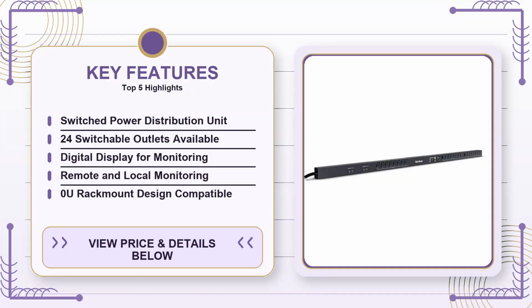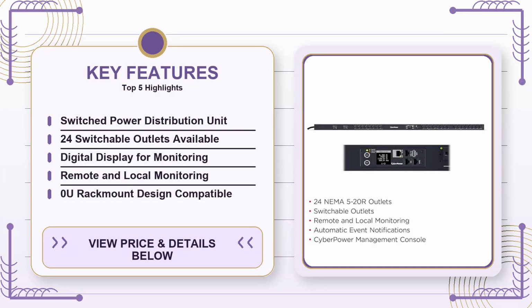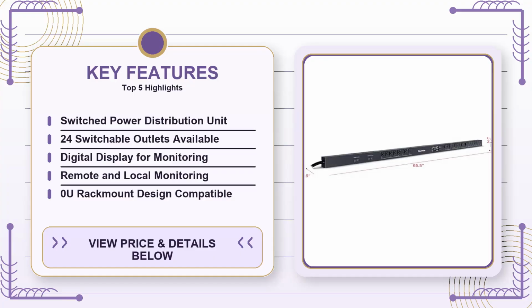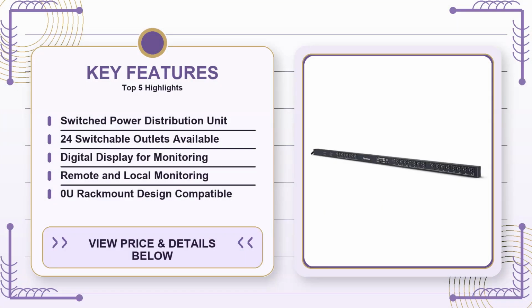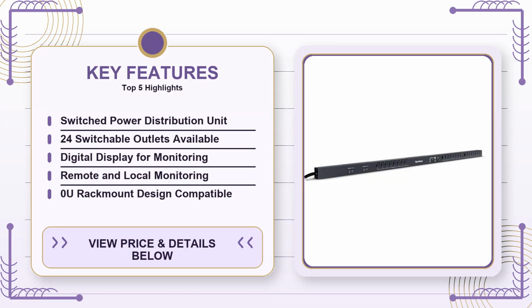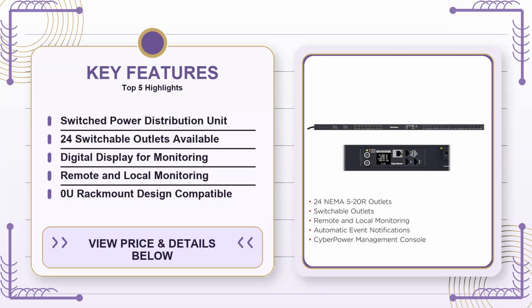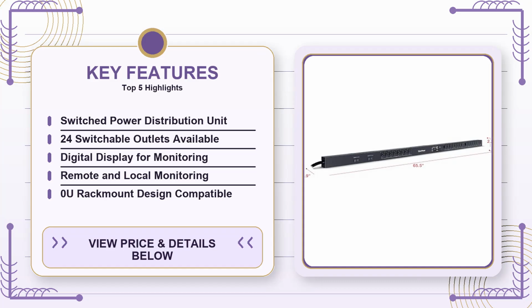Now let's talk about the practical strengths. The biggest win for me is the truly 0U footprint. Because the unit slides into the side of a 19-inch rack without taking up any vertical space, you can keep that rack height for actual equipment rather than just a power strip. In a 4U or 6U rack, every millimeter counts, and the PDU sits comfortably against the side rail, freeing up space for airflow. The digital display sits on the front panel and shows voltage, current, and load percentage, letting you see at a glance if you're approaching that 24A ceiling. For anyone who has ever had an unexpected overload and had to pull the whole rack down to check, that visual cue is a genuine safety net.